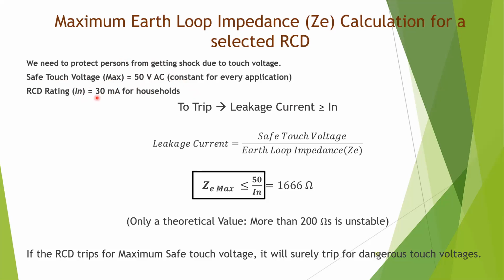And our RCD rating for households is 30 milliamperes. So we need to calculate the earth loop impedance required to trip this RCD at 30 milliamperes. It is a very easy calculation. You can use this equation, which is simply V equals IR. We take I as 30 milliamperes, V as the safe touch voltage, and R as the earth loop impedance.